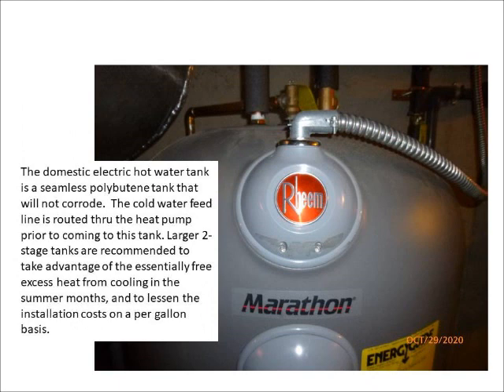The domestic electric hot water tank is a seamless polybutene tank that will not corrode. The cold water feed line is routed through the heat pump prior to coming to this tank. Larger two-stage tanks are recommended to take advantage of the essentially free excess heat from cooling in the summer months and to lessen the installation costs on a per-gallon basis.